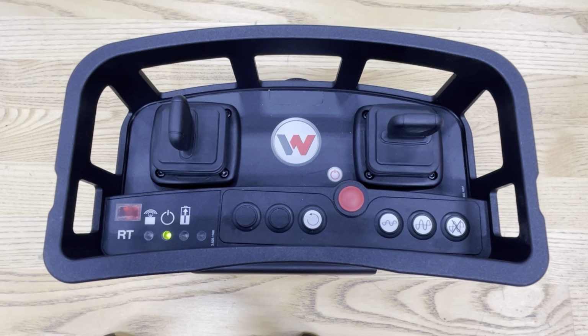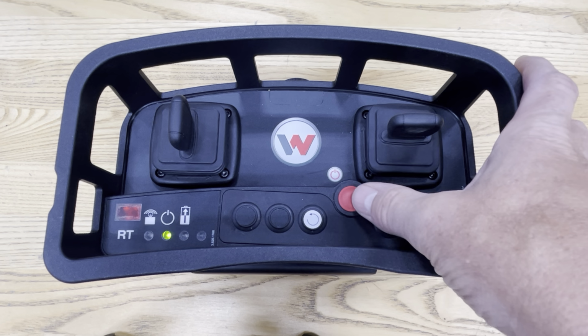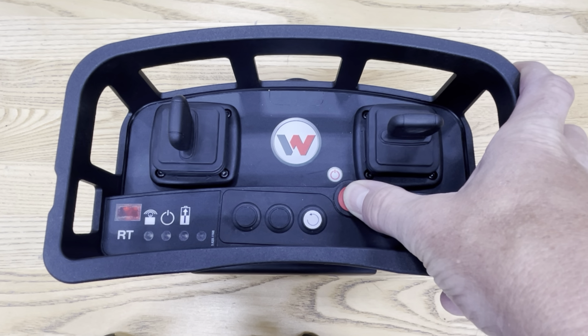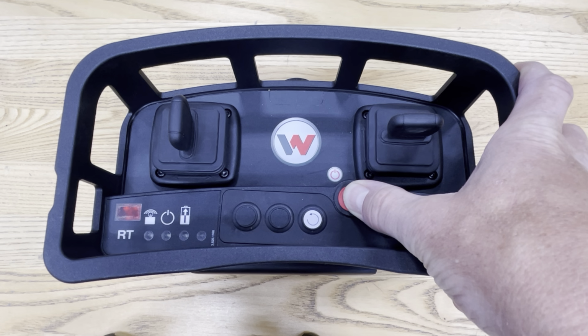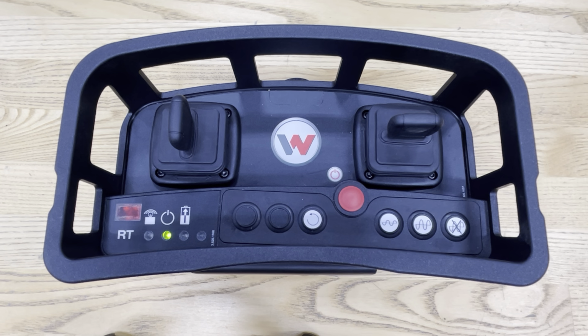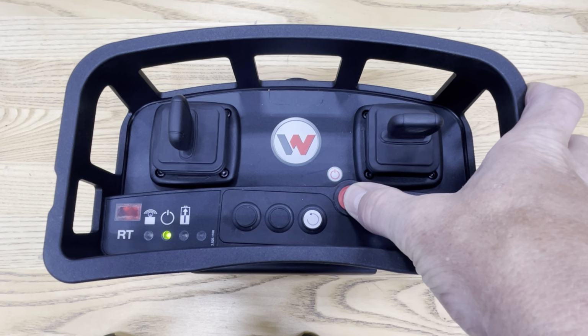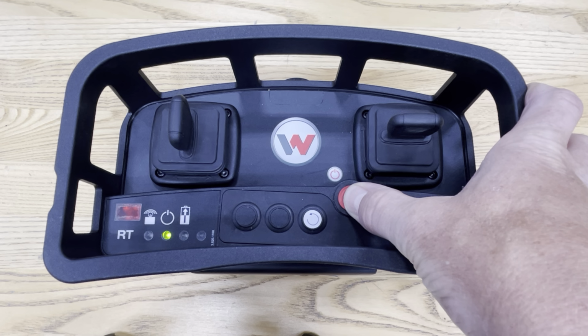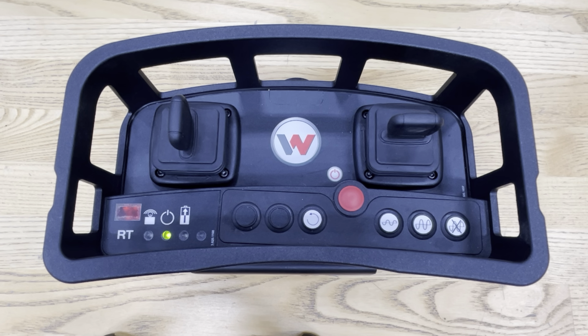So the transmitter is on. I'm going to press and hold the power button for 5 seconds. If we watch that power LED lamp, I let go after 5 seconds, and now we're at a solid green state. I'm going to press and hold again for 5 seconds, and then we will see that rapid flash of the green LED power lamp on the transmitter. That rapid flash indicates that I'm in calibration mode.